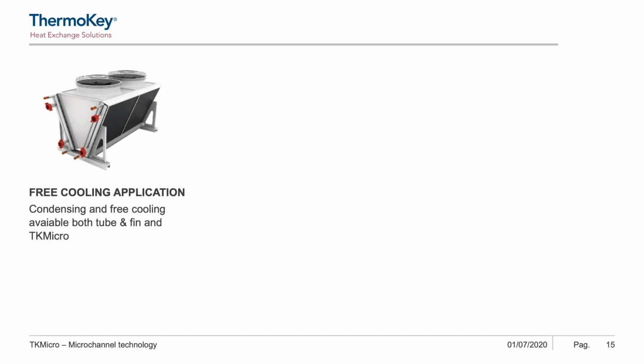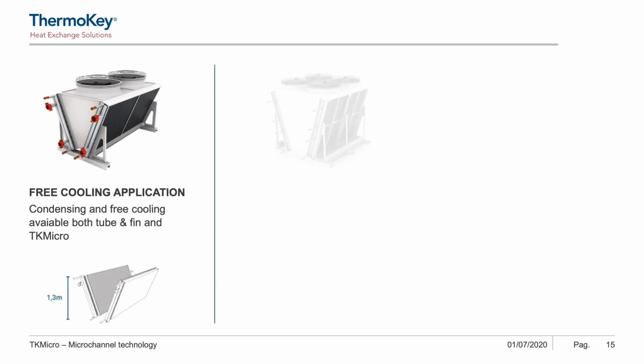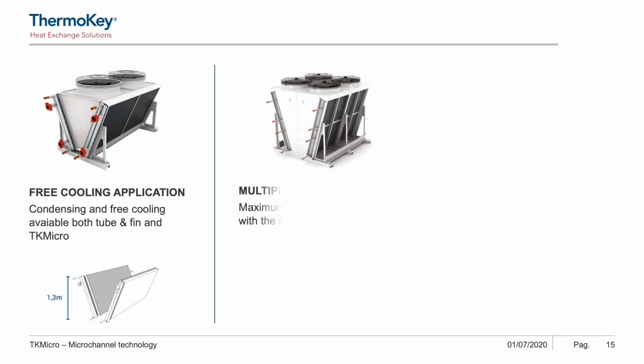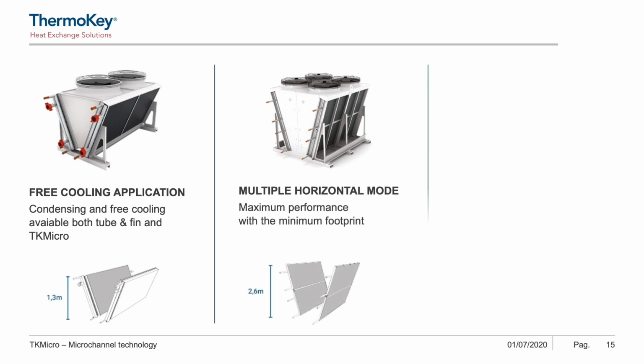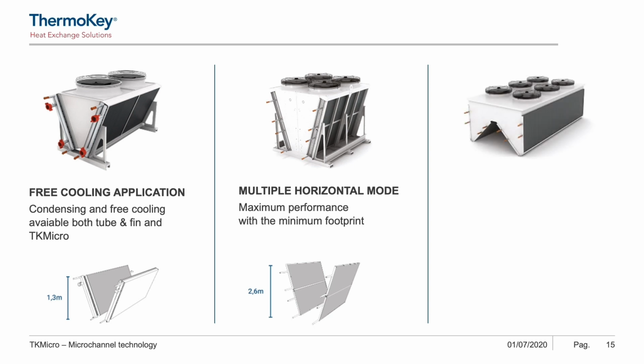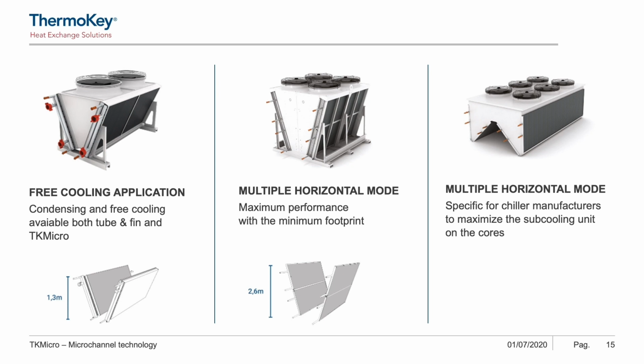Other possibilities consist in combining water and refrigerant microchannel cores in order to create a so-called free cooling module. Multiple microchannel cores can be stacked in a shape of a multiple horizontal mode in order to increase and maximize the performance within the minimal footprint. Finally, a typical upside-down M-shaped module can be manufactured with a maximum length of 4 meters.